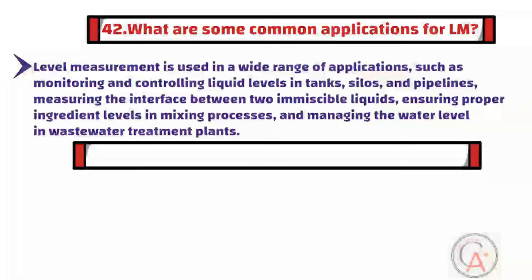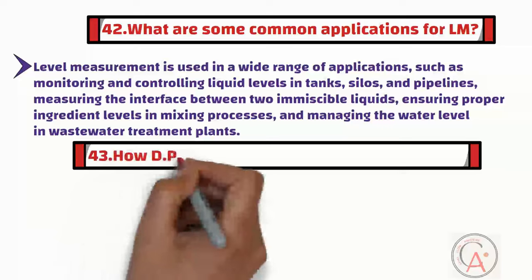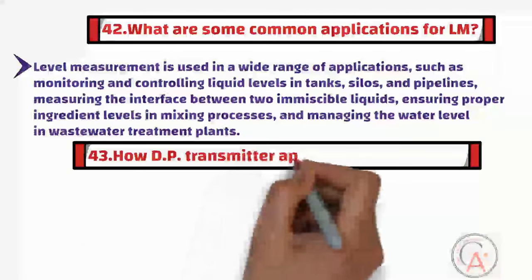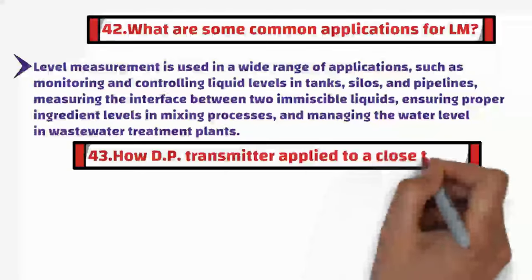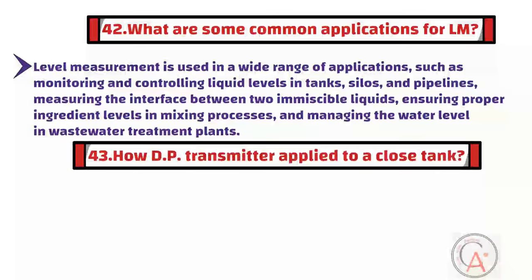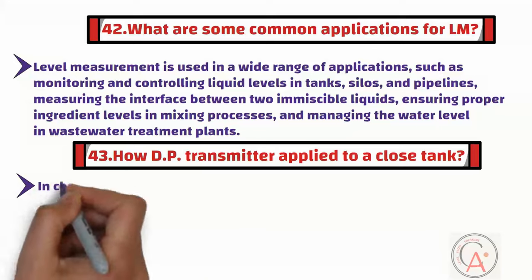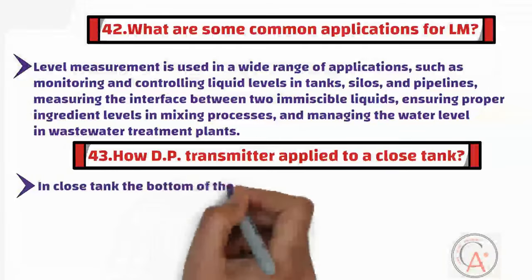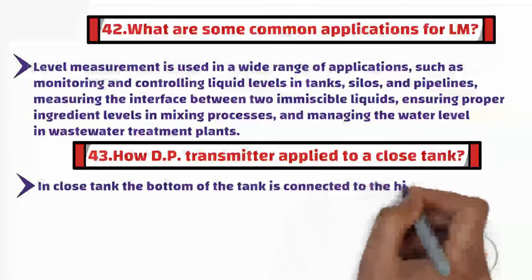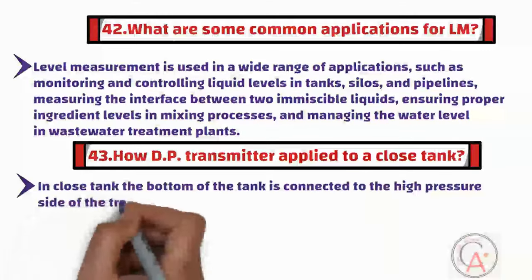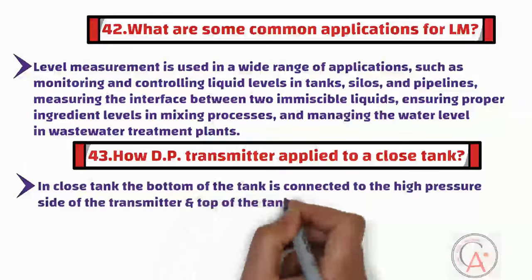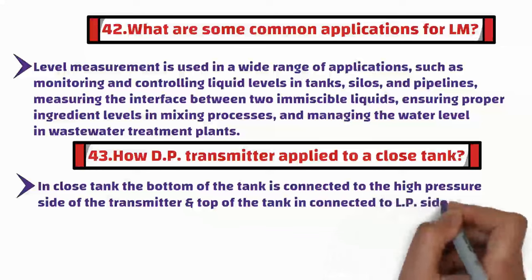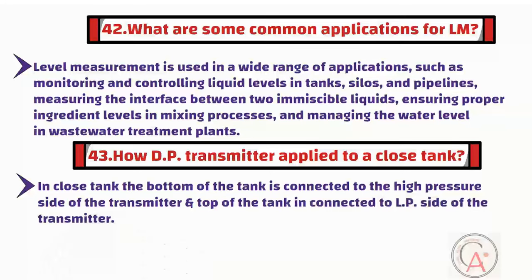Question forty-three is: how is the DP transmitter applied to a closed tank? In a closed tank, the bottom of the tank is connected to the high-pressure side of the transmitter, and the top of the tank is connected to the LP side of the transmitter. In this way the vessel pressure is balanced.